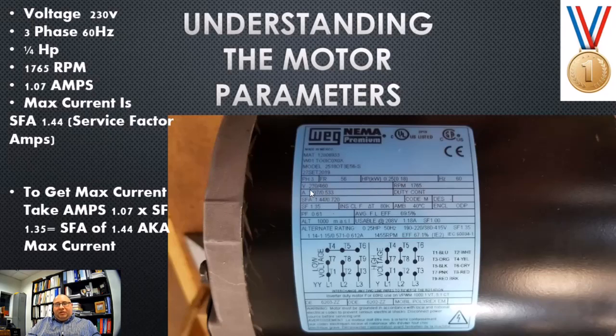We have to choose our voltage. This is the output voltage, and this particular VFD drive will produce 230 volts, so it's a 230 volt motor. And we have something here called amperages and service factor amps. This is nice because this particular motor gives you your service factor amps. Your service factor amps is the maximum current that the motor is rated for. Service factor has to do with how clean and efficient the motor runs. Typically, you'll see a service factor of 1.15. This particular motor has a service factor of 1.35, so it's a little bit noisier and dirtier. But keep in mind that this is only a $100 motor, and it's three-phase, so keep that in consideration. We got it from Johnstone. If you did not have the service factor amps, and a lot of motors do not, you will take the normal running load amps of 1.07 and multiply that by your service factor, which is 1.35.